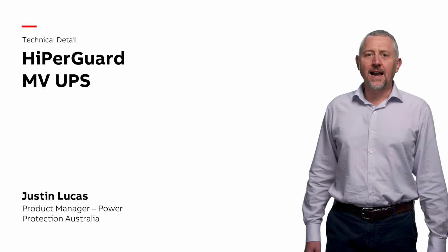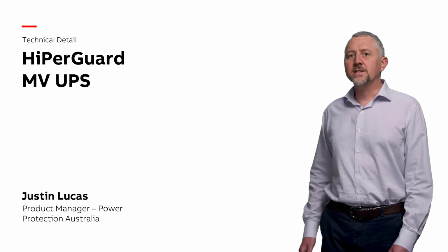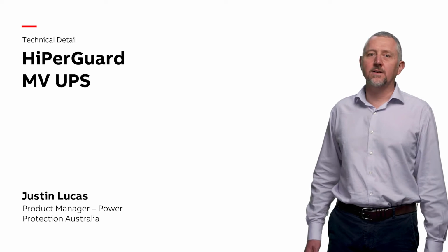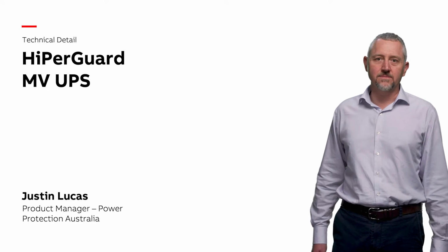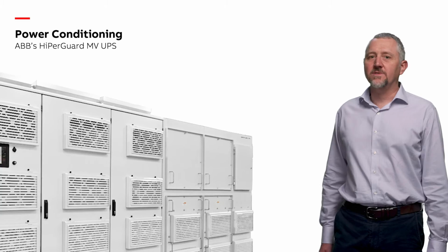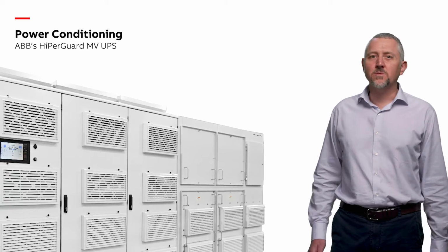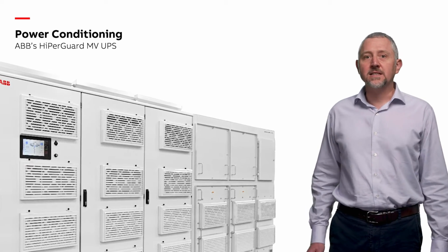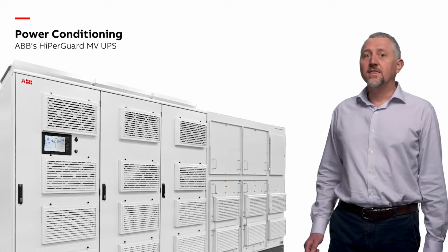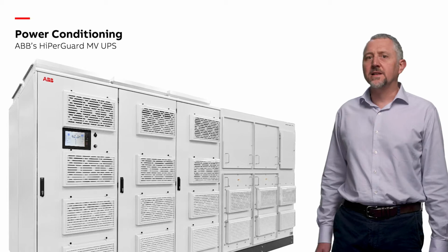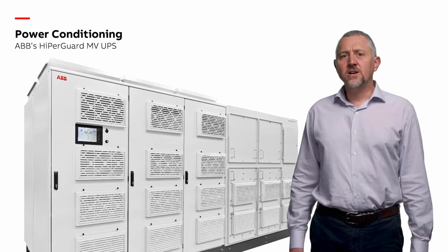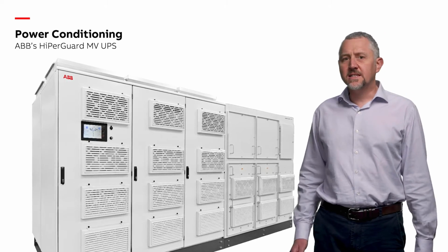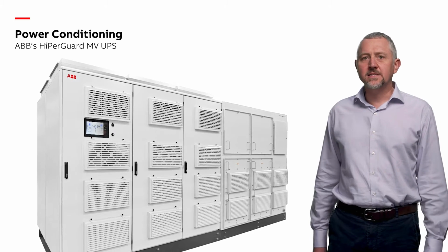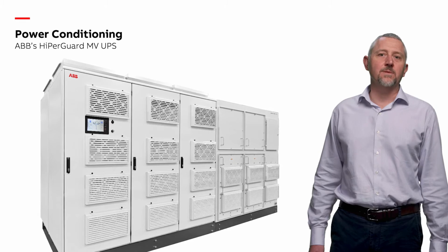Now I'm pleased to introduce our expert, Justin, who will guide us through the intricate details of the HiPerGuard MV UPS. Thanks, Adam. ABB's industry-first medium-voltage UPS provides continuous and reliable power supply up to 24 kilovolts, intended for multi-megawatt power protection. ABB's ZISC, Impedance Isolated Static Converter, is a high-performance power conditioning and uninterruptible power supply architecture. Based on an isolating line reactor paired with advanced ABB power converters, this simple yet robust design ensures unmatched reliability and efficiency. The ZISC architecture operates independently from the utility, continuously conditioning and filtering line disturbances, voltage imbalances, and addressing load-related events with high overload capability.